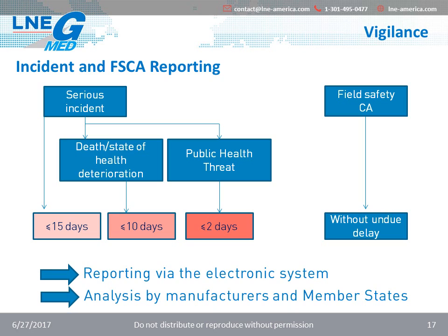In these articles, we can identify that many provisions are coming from the MedDev 2.12-1 Revision 8 related to guidelines on a medical devices vigilance system. So what was in a guideline in the directives has now become requirements within the new regulation.